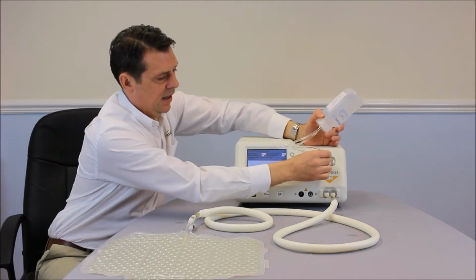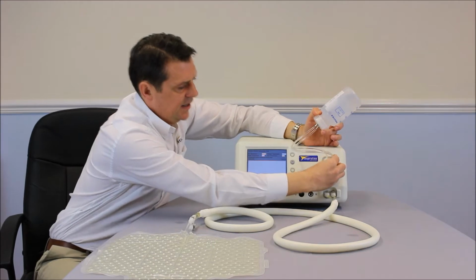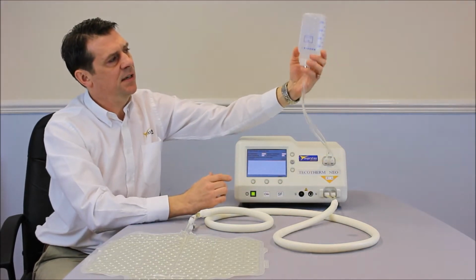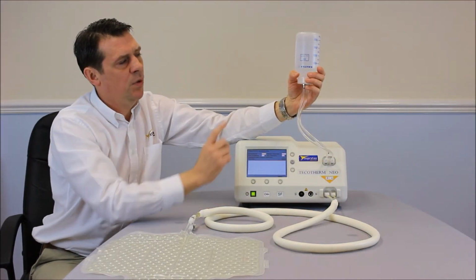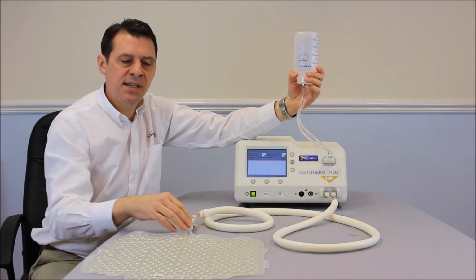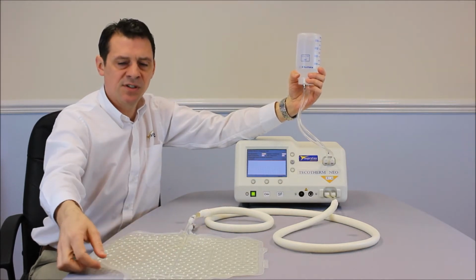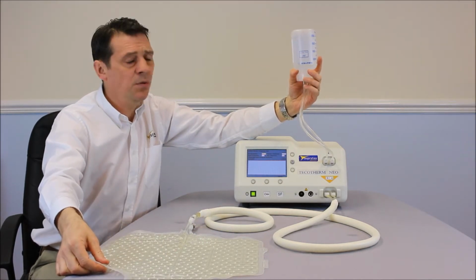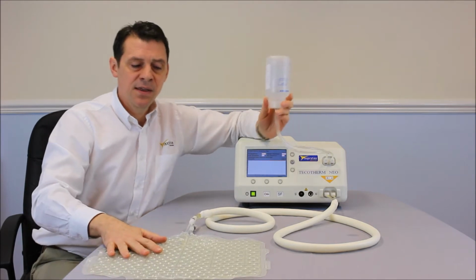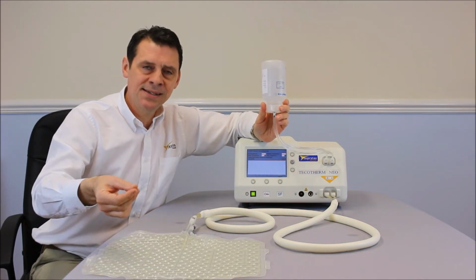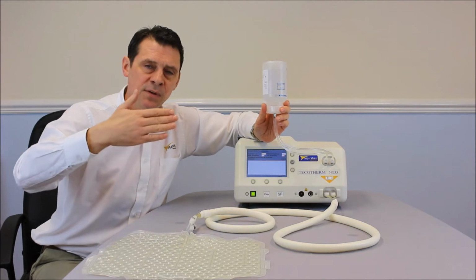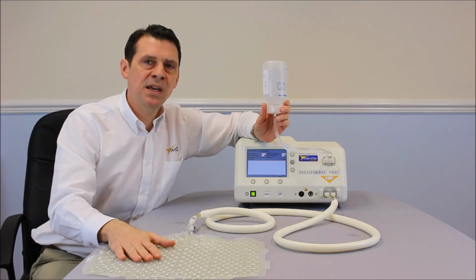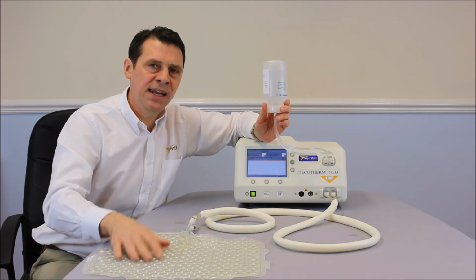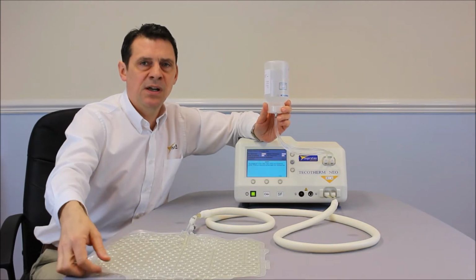If I connect both of these and hold it upside down, you'll see that we start to have an ingress of water. When the water's coming in, we know that the fluid is then being displaced into the mattress. We hold this up until we've got enough fluid in here that we're happy that there's going to be consistency which is quite firm, allowing the fluid to go under the baby whilst it's being cooled. If there's not enough fluid in here, the machine won't work as well as we'd like.